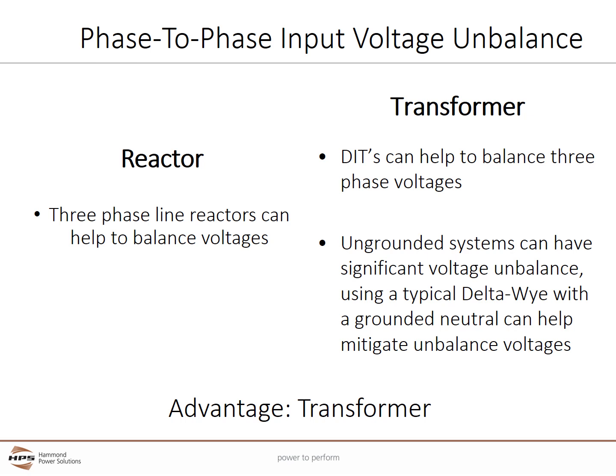Both line reactors and transformers can help mitigate the extra heating of VFD components that unequal voltages can cause. However, DITs have better performance and create a grounded Y neutral system on their secondary. While both can work, DITs are preferred when phase-to-phase input voltage imbalances are occurring.